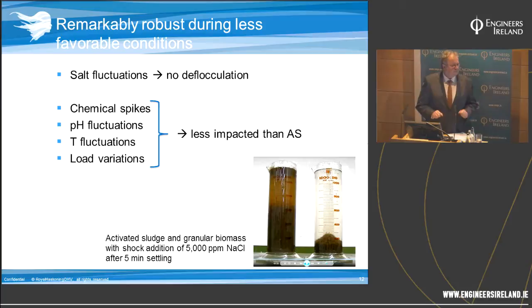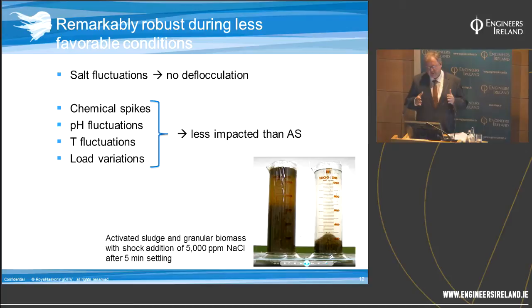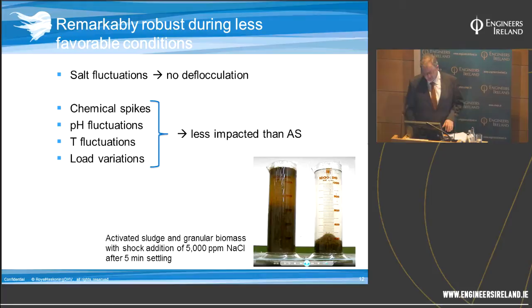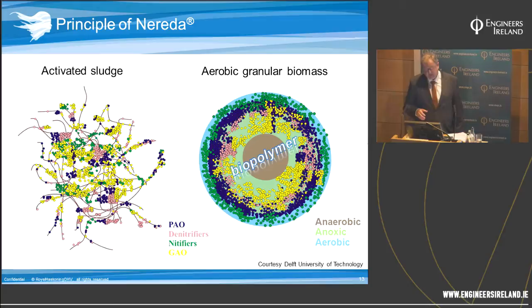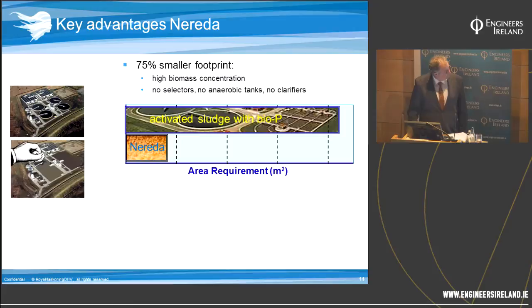The granular sludge responds remarkably robustly to less favourable conditions — shocks in salt concentration, very high or low pH, or chemical and toxic spikes. We know this because in a few cases we ran conventional activated sludge systems in parallel to a Nereda reactor. The robustness is thought to work because on the activated sludge floc organisms are exposed, whereas in the granular sludge the organisms build a polymer house for themselves — the biopolymer matrix — which protects them against shocks from toxics or pH changes.